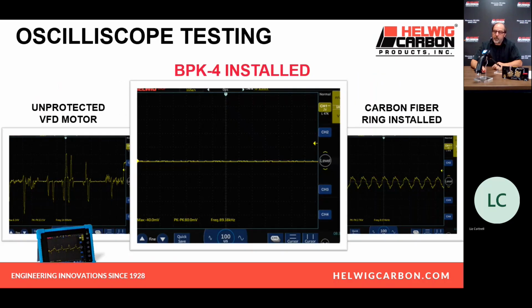If you're going to use the oscilloscope, if you're going to go beyond a straightforward test result, risk analysis that this gives you, if you want to go more in depth, you hook this to the oscilloscope. And here are some typical readings you might see on an unprotected motor on the left. Each one of those spikes is a discharge. Each one of those is an arc and is ruining the bearing. On the right, you see if you install a brand new carbon fiber ring, you can see that it does help make things better.